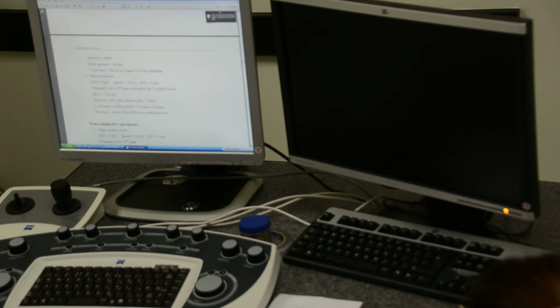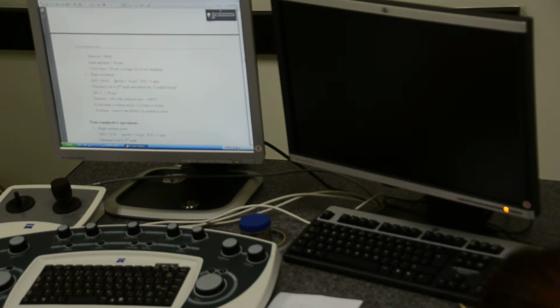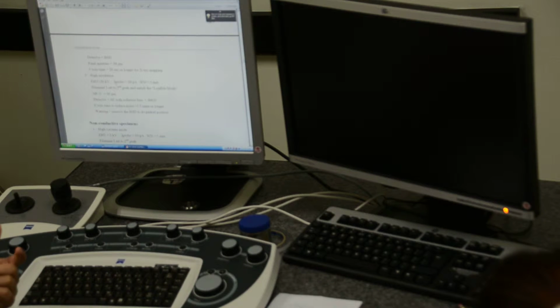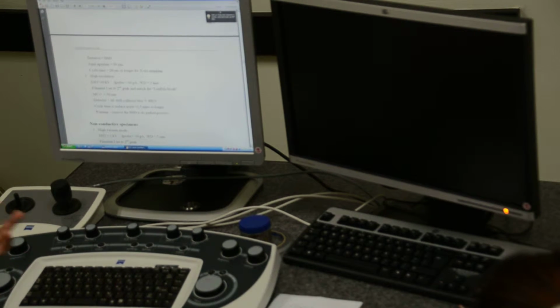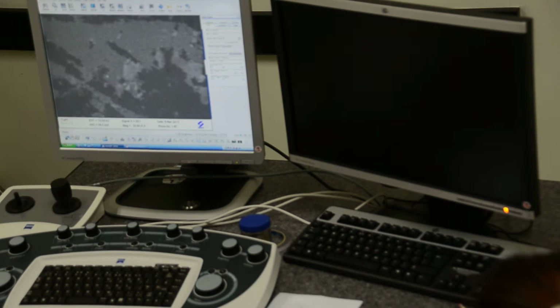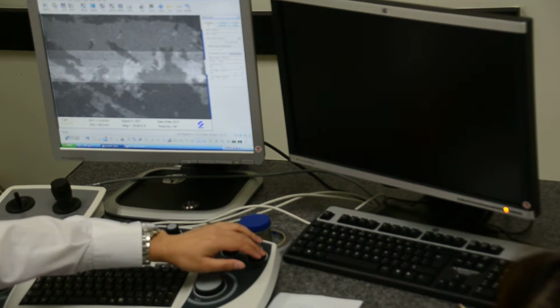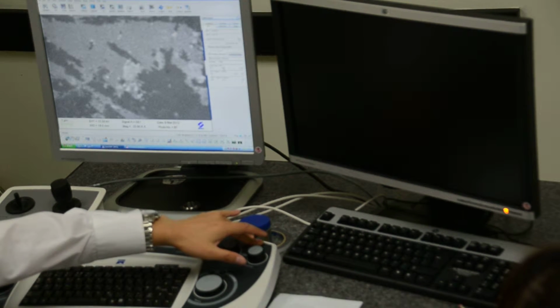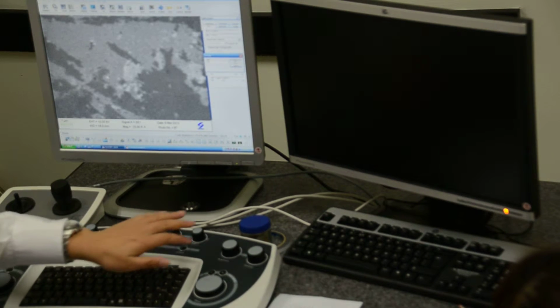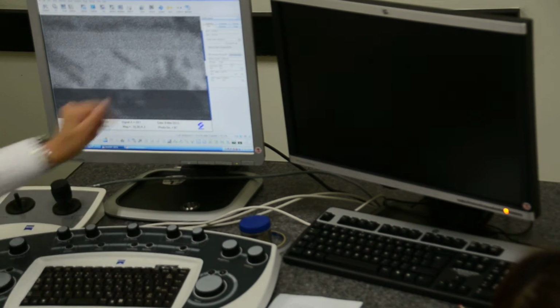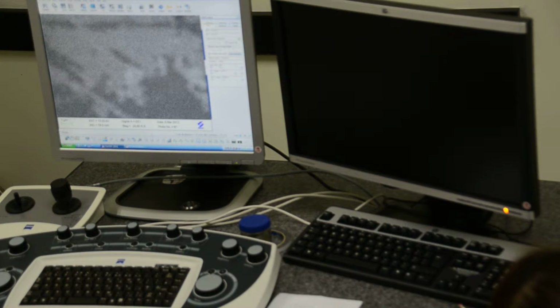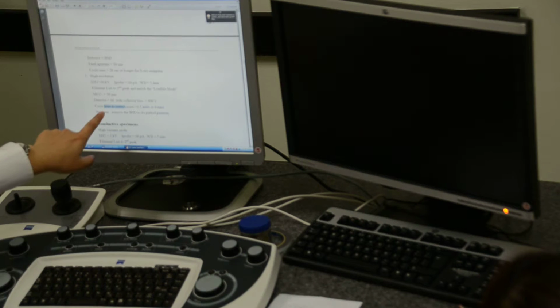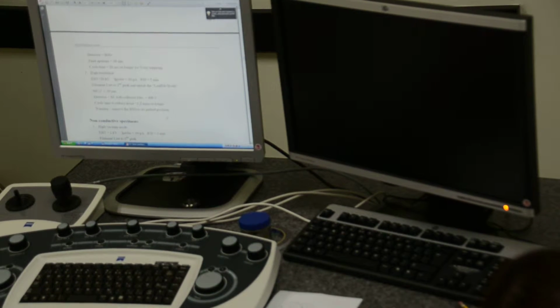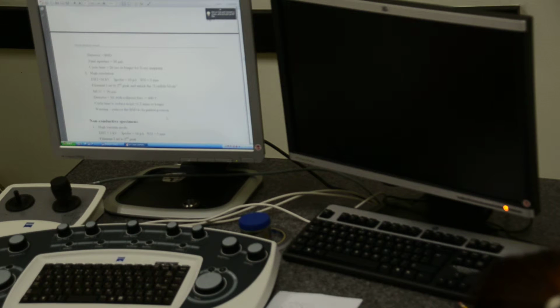The user guide tells you that if you want high resolution, go to a smaller probe current. Maybe 10 picoamperes is quite small. Normally I go to maybe 50 picoamperes, then you still get reasonable resolution and a reasonable signal to noise ratio, because now it's very noisy as I dropped my probe current a lot. If I really go to 10 picoamperes, it's very noisy. So that's why it tells you to cycle a longer time, about 1.3 minutes, about 3 or 4 times longer.